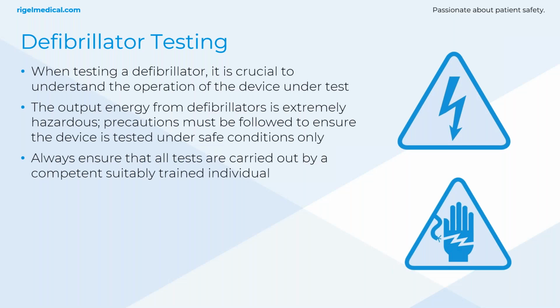So we've covered what the defibs do, how they work, when to use them, but how do we go out there and test them? Most of the time they just sit on a shelf on a wall somewhere until they're required, but they do need regular testing and maintenance just to make sure that they're performing when they're needed. It's serious high voltage equipment as well, so it goes up to 360 joules on some of the older defibs, 200 joules for most of the modern ones, and obviously that's more than enough energy to cause serious injury. They are designed to restart the heart, so you can imagine if you handle them improperly when you're testing, then it's quite a serious consideration.